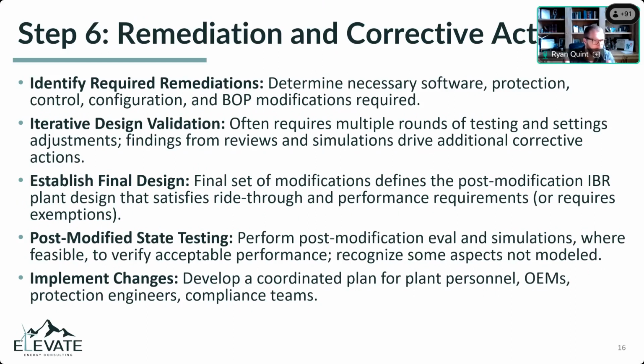Because if it's a model issue, am I compliant? My simulation doesn't prove I'm compliant even though the OEM says what's out there is compliant. So you run into complications of what to trust, what to use - and now we've created a model verification, model validation exercise, when in reality we're just trying to prove the plant will ride through, which all indications show it does. That's where complications show up practically, making sure all corrective actions are laid out in a reasonable, effective way.